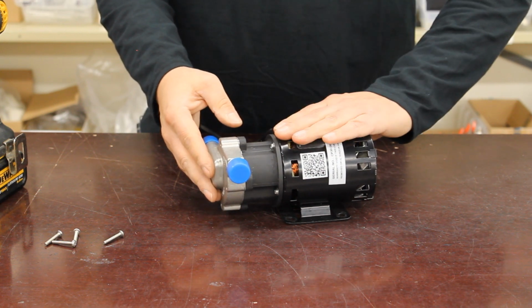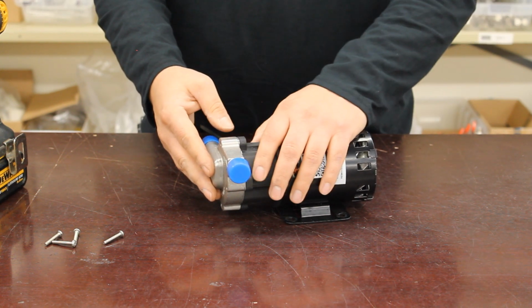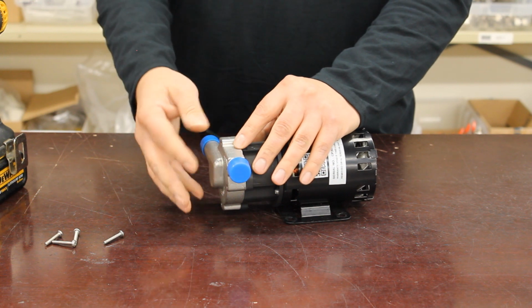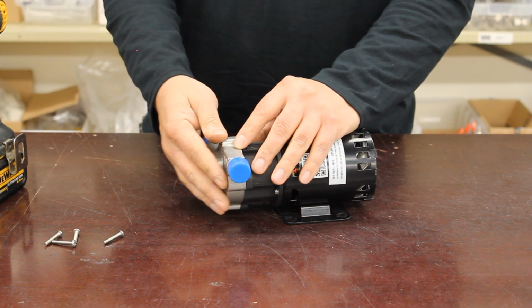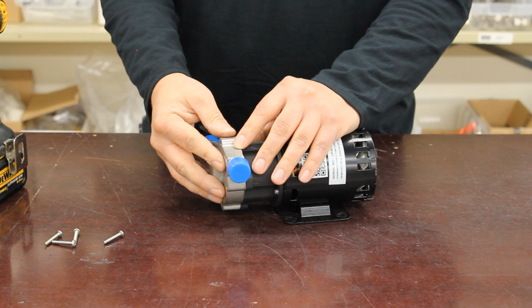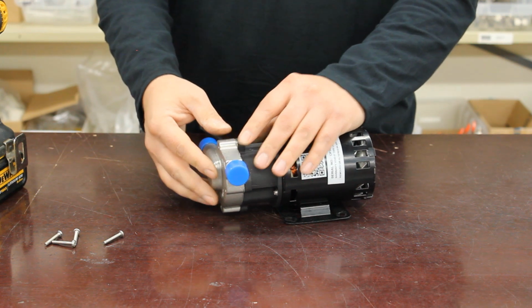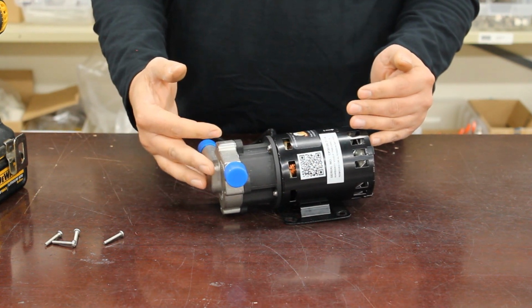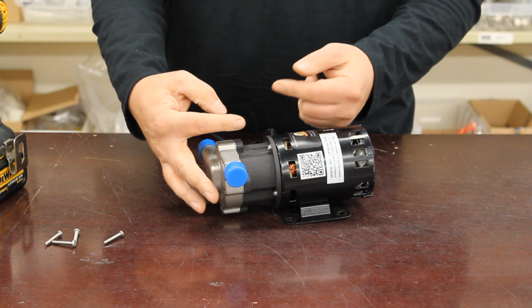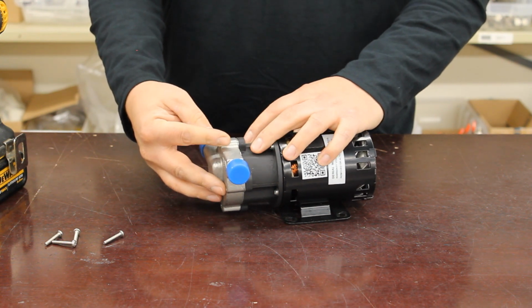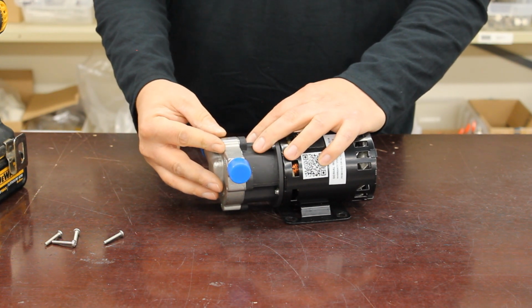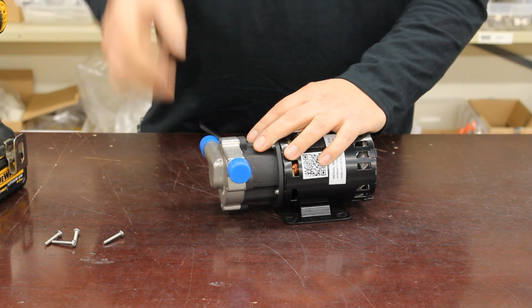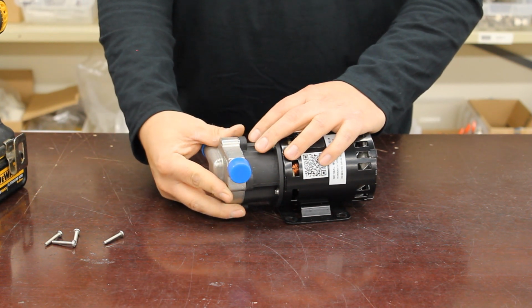If the pump motor is spinning, but no liquid is pumping, and you're sure there's liquid in the head, then something must be obstructing the impeller from turning. Again, because these are magnetically driven pumps, there is that magnetic coupling that's made between the cup magnet and the impeller magnet, which can be broken and therefore not move the impeller at all.